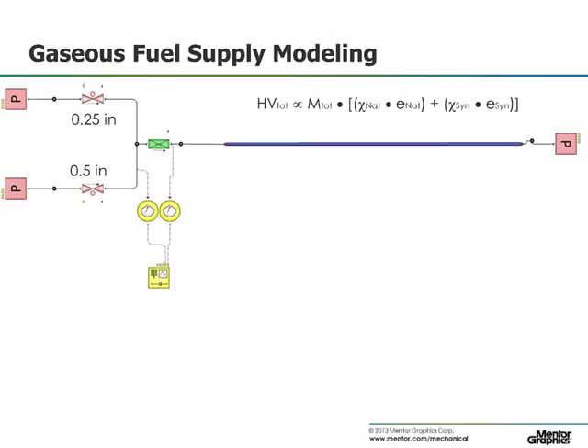We can perform this same calculation in situ in the Flowmaster model by using gauge components to measure concentration and mass flow rate, and then use a control along with a script to do the actual arithmetic. We can then plot results of heating value coming out of the controller just like any other standard Flowmaster result.